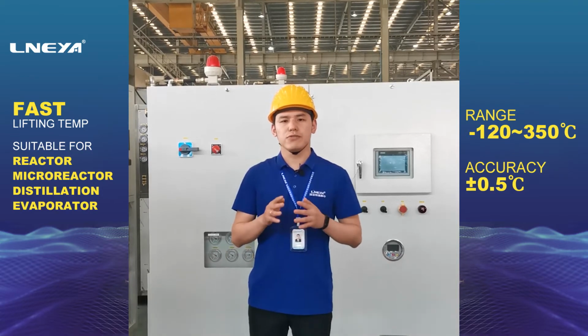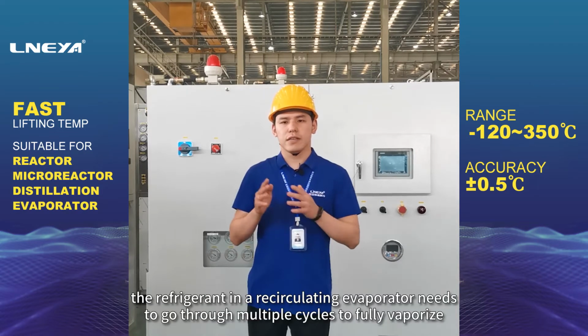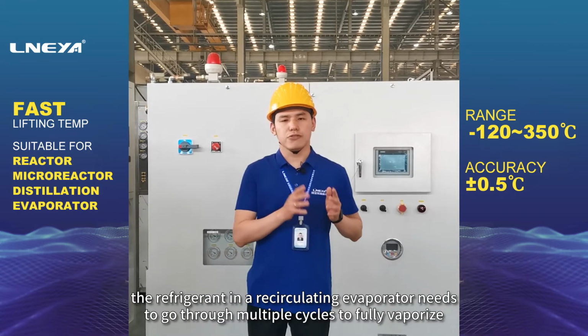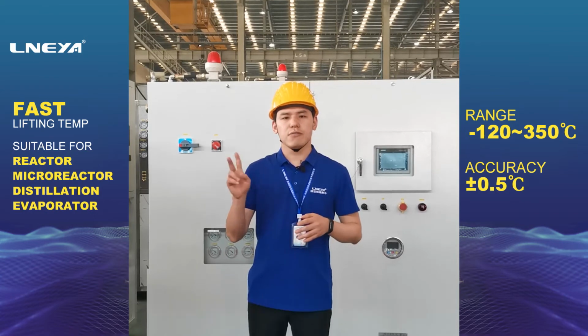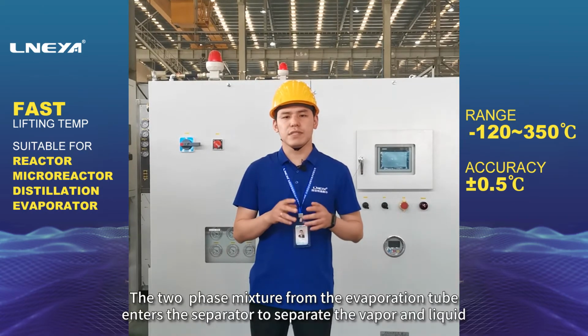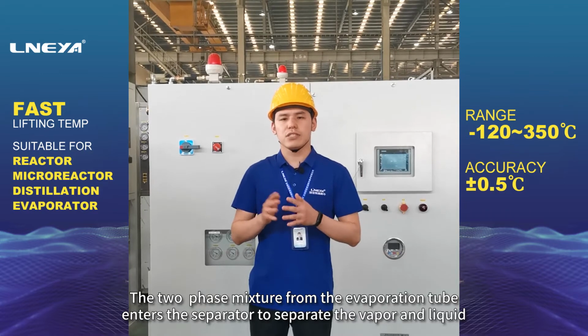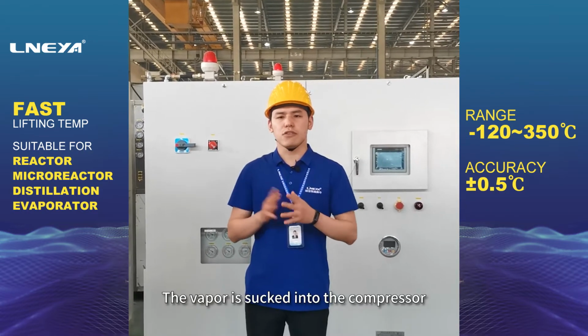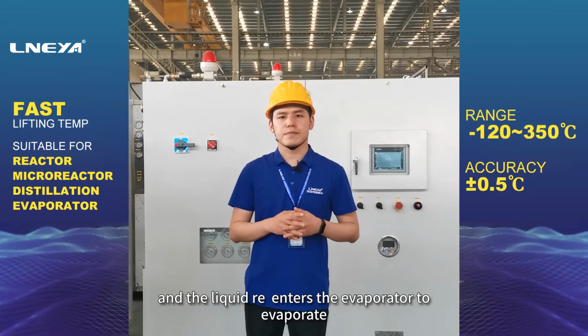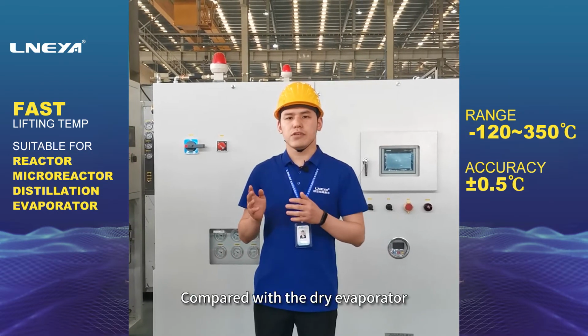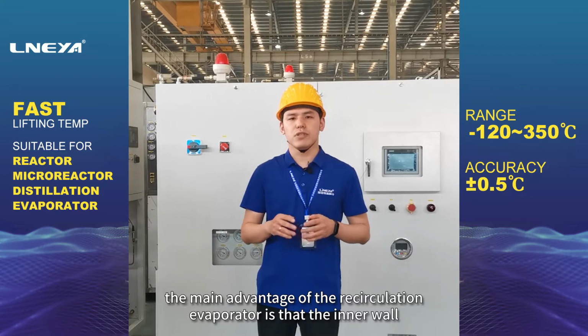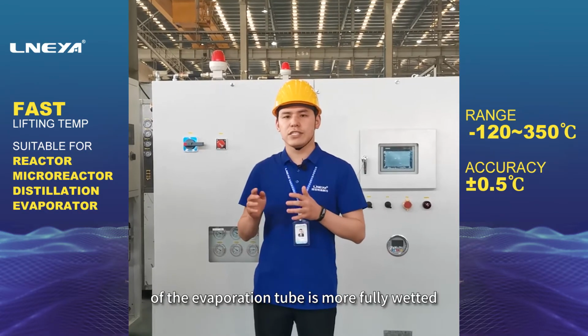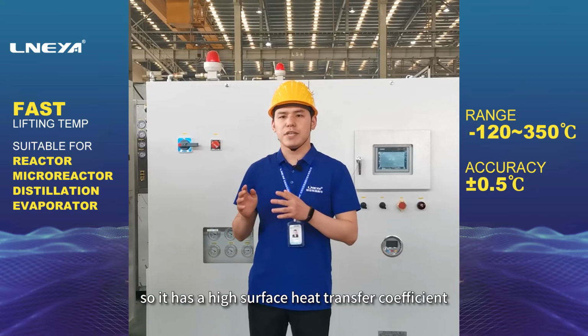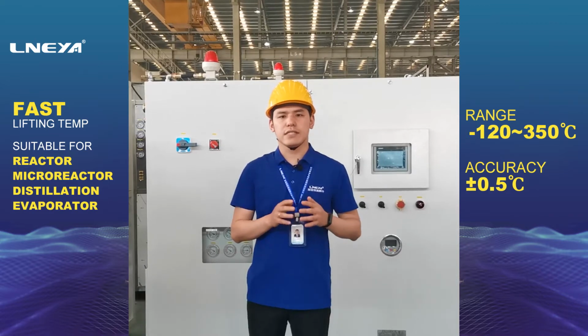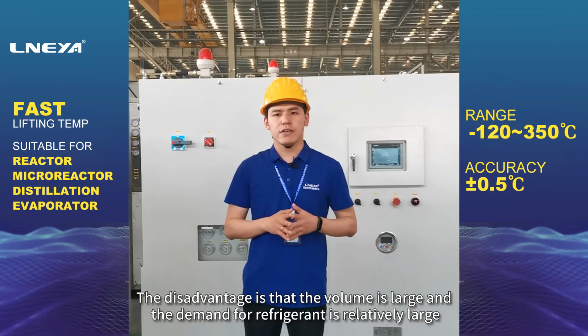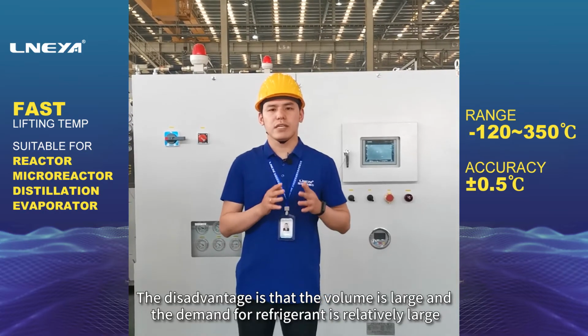Recirculating evaporator. As the name implies, the refrigerant in a recirculating evaporator needs to go through multiple cycles to fully vaporize. The two-phase mixture from the evaporation tube enters the separator to separate the vapor and liquid. The vapor is sucked into the compressor, and the liquid re-enters the evaporator to evaporate. Compared with the dry evaporator, the main advantage of the recirculation evaporator is that the inner wall of the evaporation tube is more fully wetted, so it has a high surface heat transfer coefficient. The disadvantage is that the volume is large and the demand for refrigerant is relatively large.